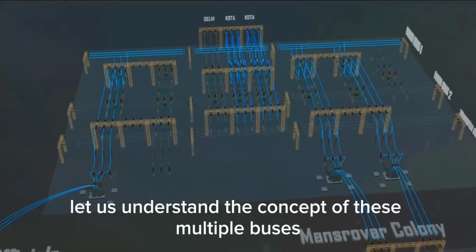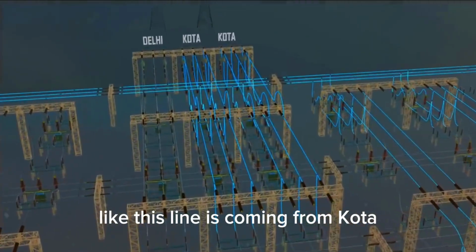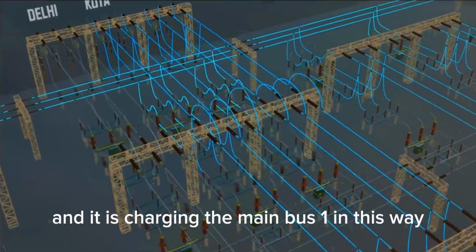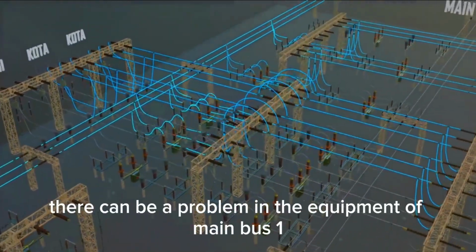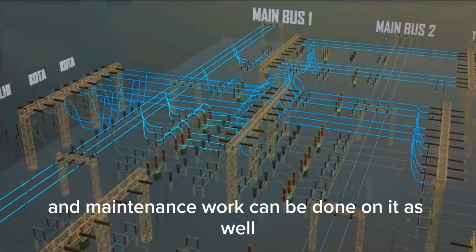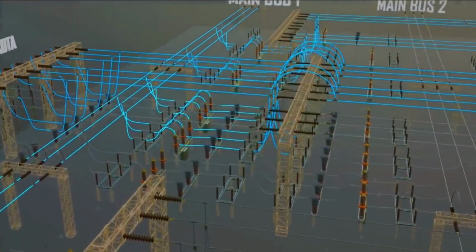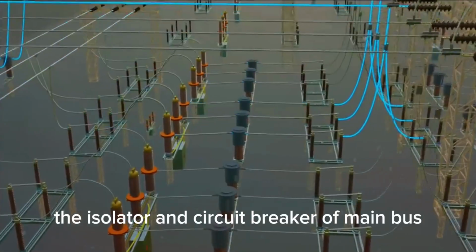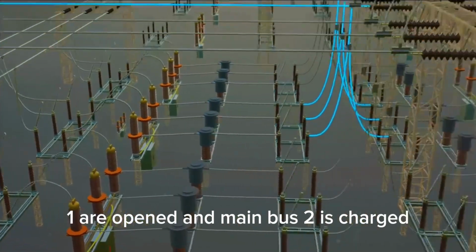Now let us understand the concept of these multiple buses. Like this line is coming from Kota and it is charging the main bus 1 in this way. But sometimes there can be a problem in the equipment of main bus 1 and maintenance work can be done on it as well. So in such a condition, the isolator and circuit breaker of main bus 1 are opened and main bus 2 is charged.